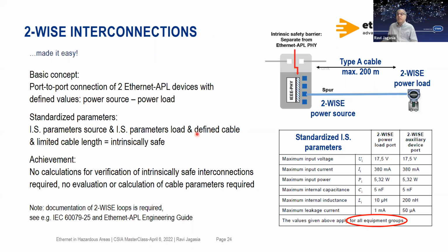Going back again to the 2-WISE connection, that's your field device, the power load, the power source, the associated apparatus, the type A cable connected over here, and then of course the standard intrinsically safe two-wire cable going up to the north side. We mentioned that there are standard IS parameters now. This is your power, your operating characteristics. So you know what is the voltage output from the power source, what is the power requirement of the field device, and you are able to ensure that you won't have any surprises there. Similarly, for the entity parameters, the capacitance, inductance, and leakage currents are all pre-specified. So you have nothing to worry about connecting an Ethernet-APL field device to the field switch.